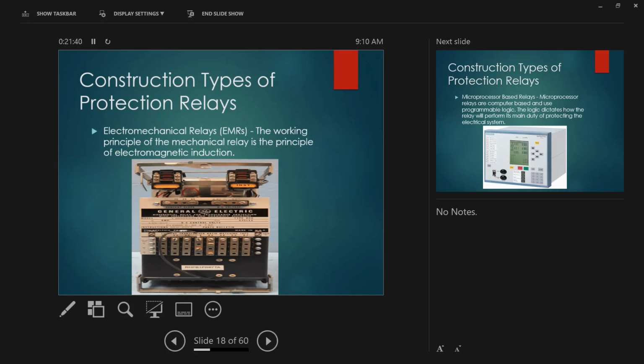Now, construction type of relay. I think for the new generation like you guys, you normally never encounter this kind of relay. But in 2002, when I began in this industry, most of the relays that I worked on were this, because most of the relays that we maintained during 2000 were designs from the 80s and early 90s. So it's really Jurassic. We didn't have the fancy software before. We just relied on our theory and how it works. So it's electromagnetic induction. Once you feed it with a small current, the disc will rotate, and you see this instantaneous coil will initiate if you have a bigger current, quicker to react. And you have this slower coil that's slower to react to trigger the trip. And you have the tap.